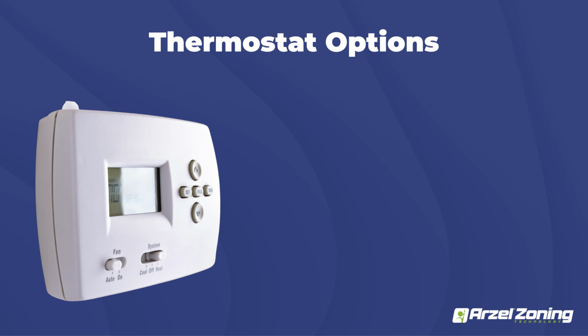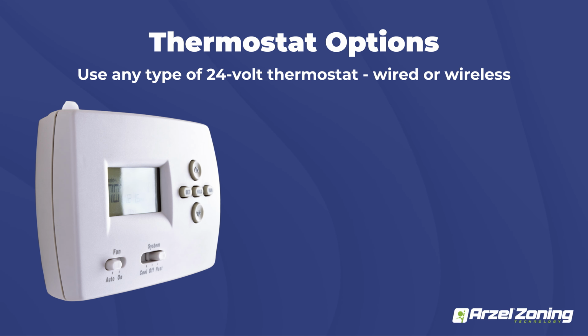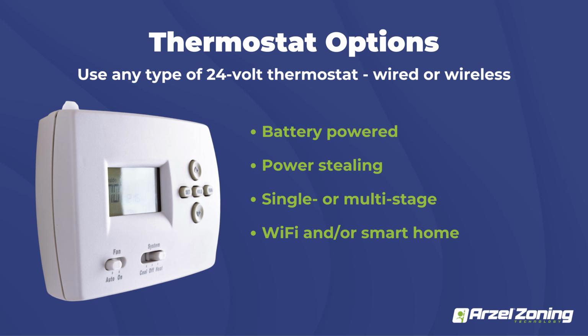As far as thermostats go, for any of our panels, we're compatible with any 24 volt thermostat on the market, whether it be a smart thermostat, Wi-Fi thermostat, single stage, multi-stage. It depends on the panel whether you're going to use multi-stage thermostats or not. We'll cover that when we get to the panel end of things. But as far as thermostats on the market, we're compatible with any 24 volt stat.